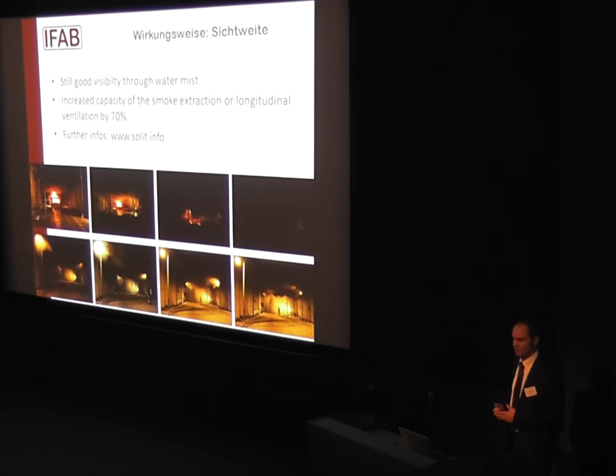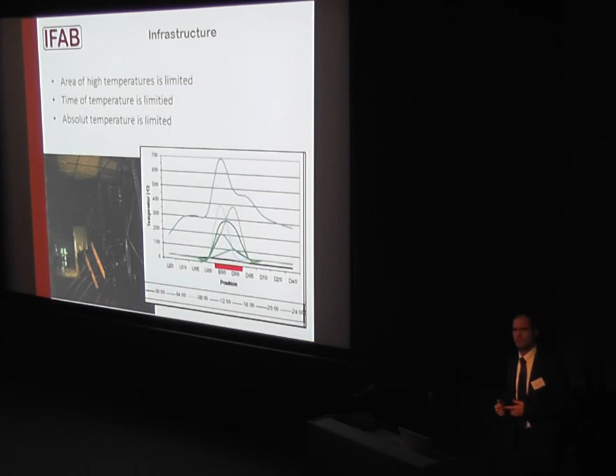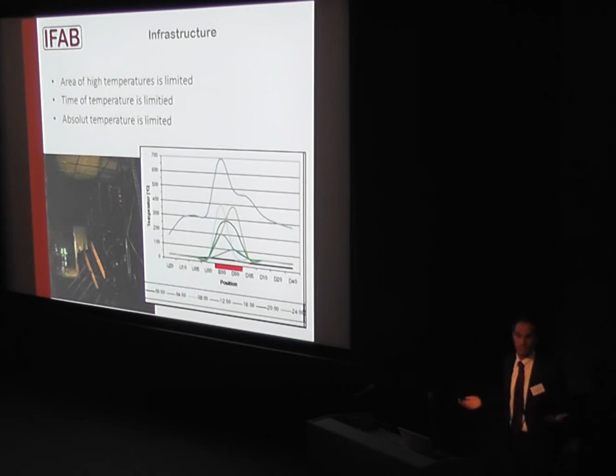That's also a point of discussion. Because of the cooling effect, on the one hand you can limit the area of high temperatures. There are still high temperatures. Around the fire, above the fire load, you still have 700, 600 degrees. You can reduce the time of when you apply the temperature because you limit the area. And the absolute temperature is limited. Remember, the RWS curve or ISO curve, it doesn't matter, goes up to I think 1350 degrees. And if you just have 700 degrees, it's a completely different story for the infrastructure. Of course, you reduce the damages.